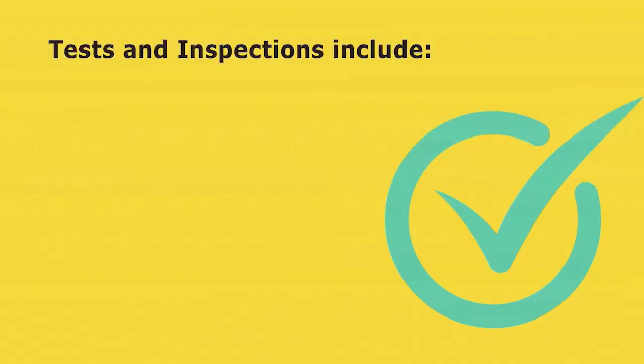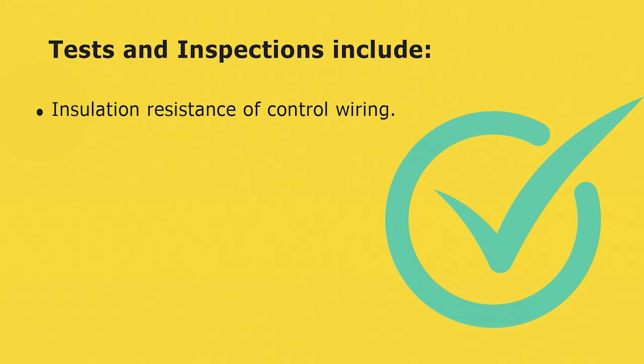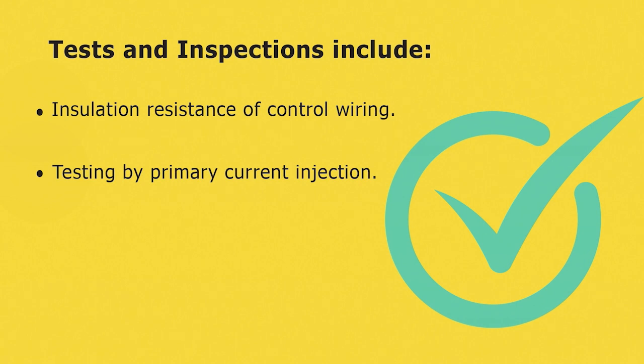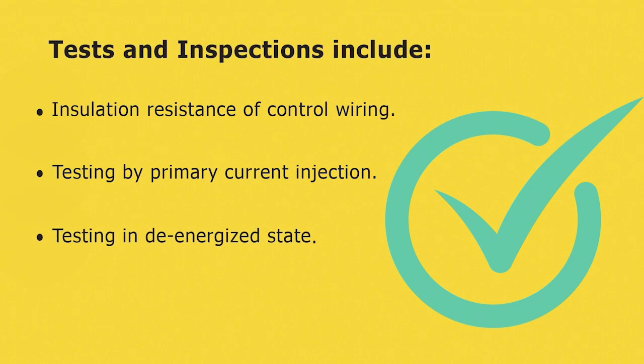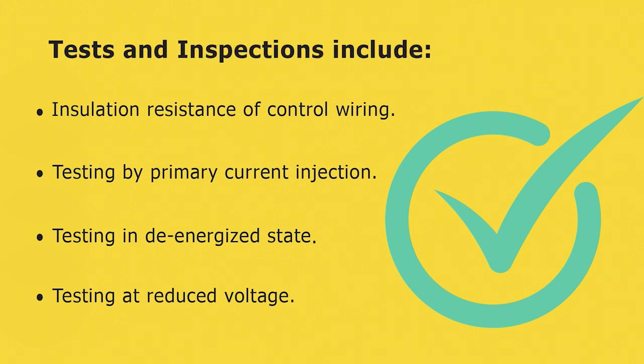One of the things we're checking is the insulation resistance of the control wiring. We want to make sure that that's intact and in good shape. We also want to make sure that it tests by primary current injection. We are going to simulate, in a de-energized state, fault current through that current transformer, throughout the whole control system, down to the relay, down to the shunt trip, and make sure that the device opens. We're going to do that at the reduced voltage like NEMA tells us to do, and we're going to make sure it all works as intended, as designed, and we're going to do that in the field. Again, simple test, easy to do.